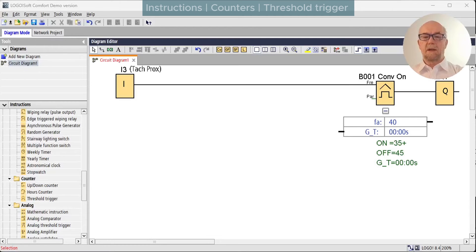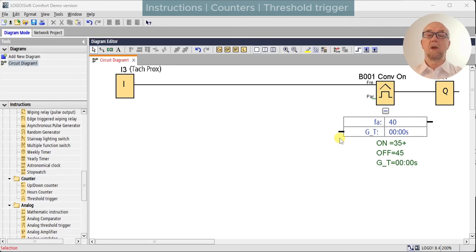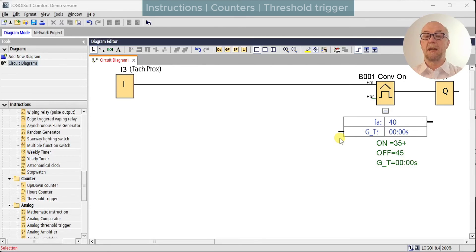As I edited the video I realized I had stated it was not possible to synchronize the gate timer with anything else in the PLC. However, there is an analog input to the gate timer setting, so if there's a way to modify that from another control we could set it to a very short gate time to re-trigger continuously — effectively holding it at zero — and then set it back to the desired gate time when triggered by another event on the PLC.